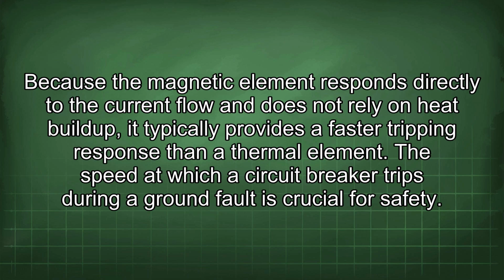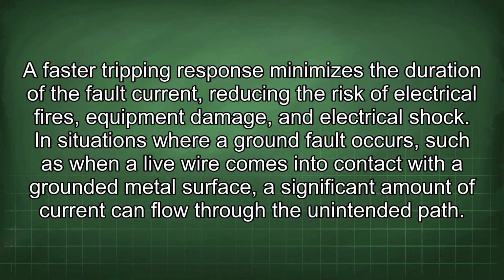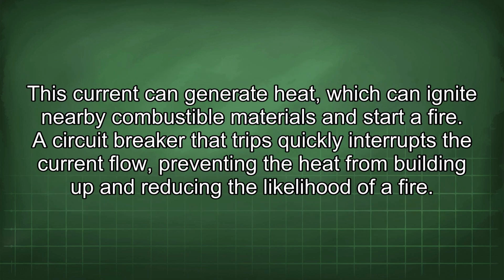The speed at which a circuit breaker trips during a ground fault is crucial for safety. A faster tripping response minimizes the duration of the fault current, reducing the risk of electrical fires, equipment damage, and electrical shock. In situations where a ground fault occurs, such as when a live wire comes into contact with a grounded metal surface, a significant amount of current can flow through the unintended path. This current can generate heat, which can ignite nearby combustible materials and start a fire. A circuit breaker that trips quickly interrupts the current flow, preventing the heat from building up and reducing the likelihood of a fire.